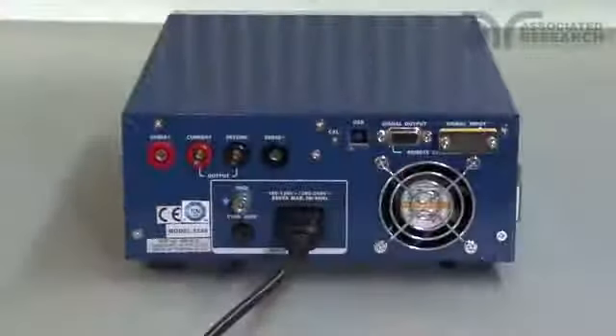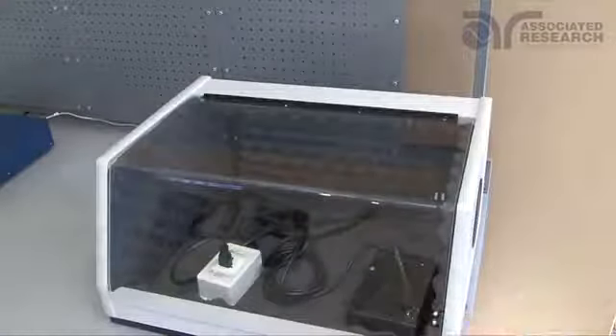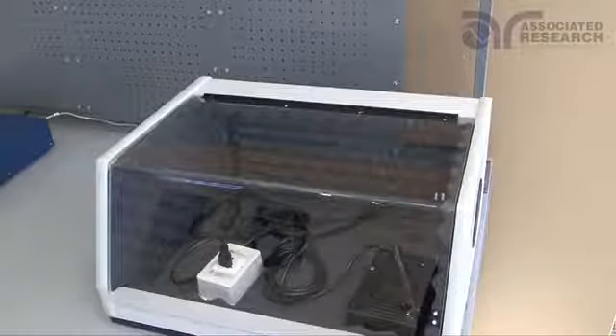You'll also need to insert the remote interlock key into the signal input terminal on the rear panel. The instrument will not output voltage without this key. This allows the user to wire the instrument to the doors of a DUT enclosure. This is a safe workstation best practice.